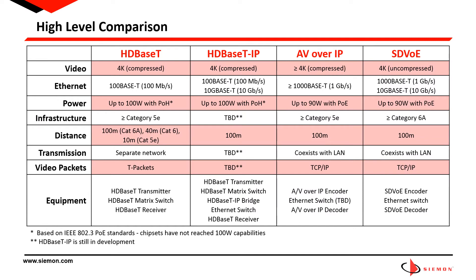As illustrated in this comparison table, proper support of 4K transmission is expected to require 10 gigabits per second transmission. In addition, with remote powering options increasing, the ideal infrastructure will be required to support high performance and high power. Specifically, Category 6A or higher performance to support full 100-meter, 10-gigabit-per-second transmission and shielded construction to optimize heat dissipation associated with remote powering, and I will be highlighting the advantage of this approach as we move forward.